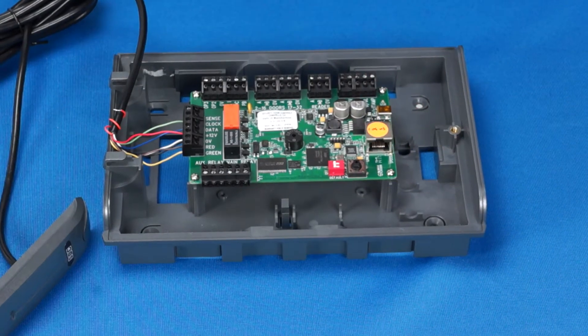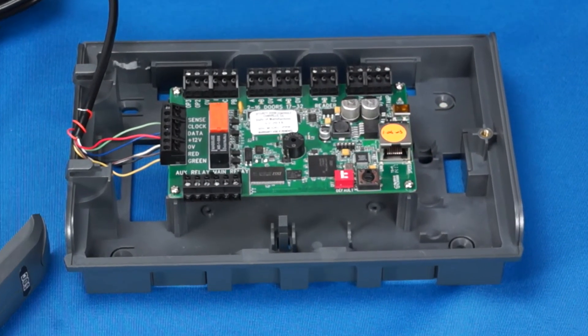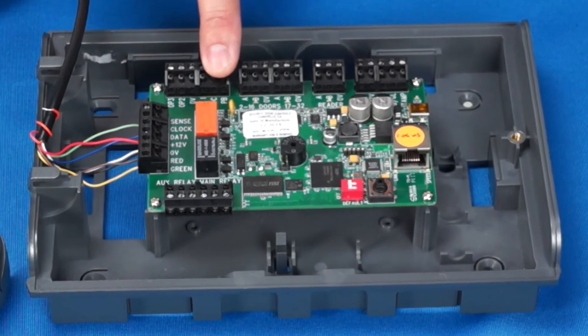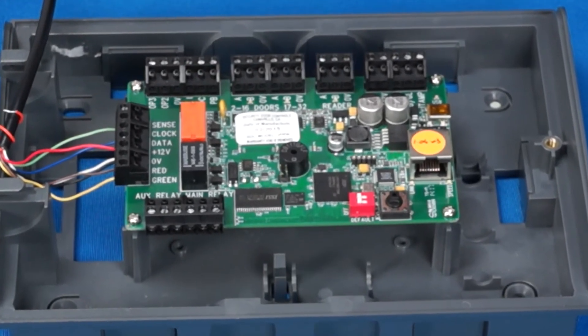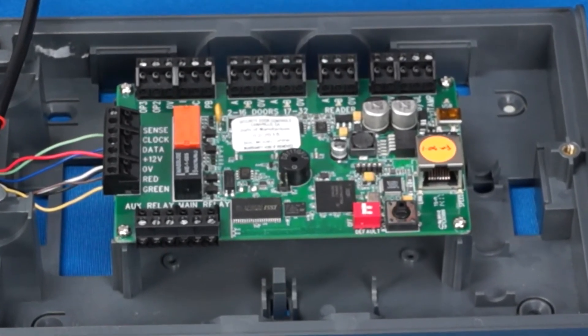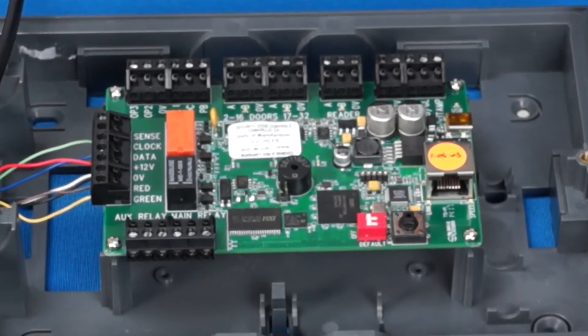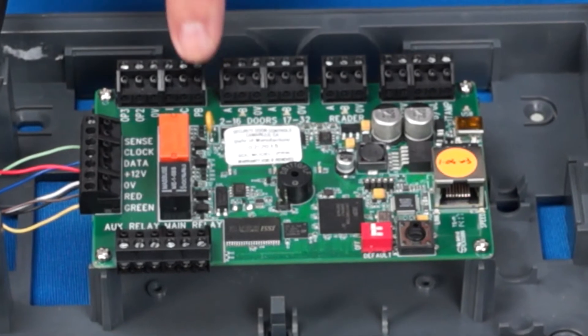If remote access is required, a normally open request to exit push button or PIR sensor would terminate here. Wire your rex across the PB and zero volt terminals.